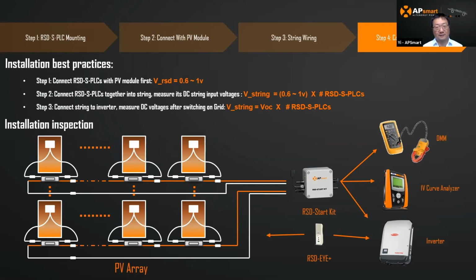The RSD-EYE+ has two major functions. One is sensing the PLC signal. The other is that it can also generate the signal, which means it's a very handy tool for troubleshooting your device. Basically, it comes with a cable connected to your device input, transmits the signal, turns on the device, and you see the voltage output to make a judgment whether this device is functional or failed. So yeah, keep that in mind, and if you have any questions, just ask me.